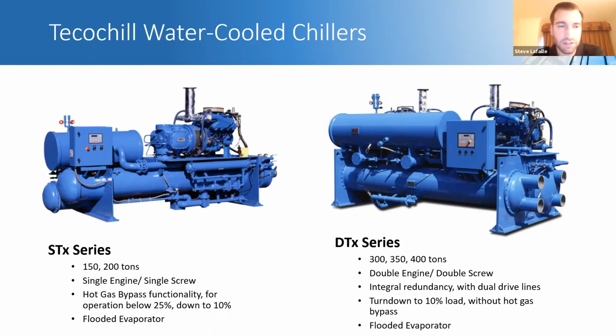The smaller chiller does have a hot gas bypass function, really only needed below 25% load. The larger chiller, we turn down to 10% without any hot gas bypass. It's all done with engine speed control. And obviously we turn off one engine on the larger machine. Now we're down to 50% load. So really important. So we have really good turn down and really high efficiency as we turn down.